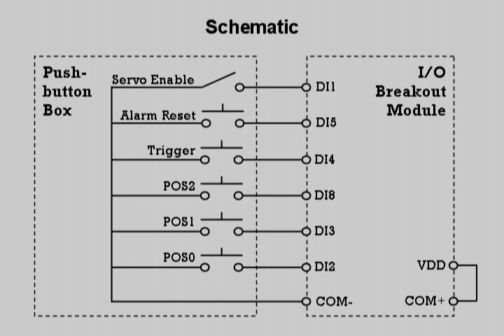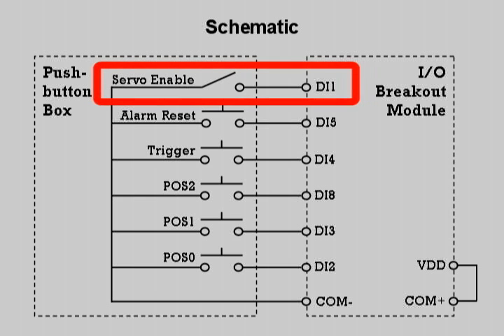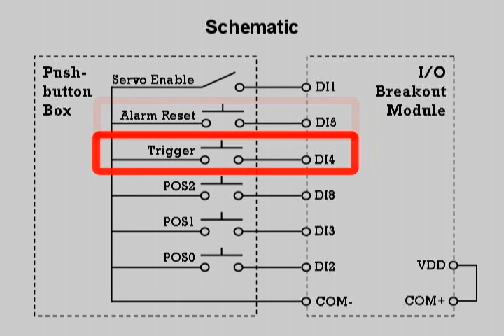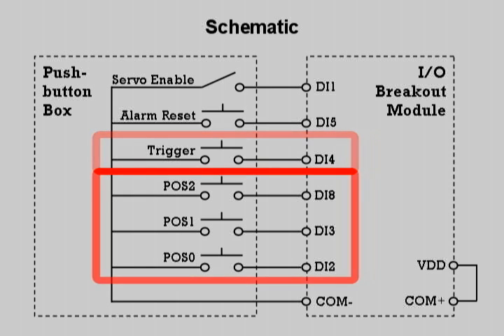Here is a schematic that shows our connections. For all the buttons and the switch, I've wired one leg of each to the COM minus connection. The switch is connected to digital input 1, this will be the servo enable. The black momentary button is wired to digital input 5, this will be the alarm reset button. The green momentary button is wired to digital input 4, this will be the trigger to actuate the moves. The three maintained buttons are wired to DI2, DI3, and DI8. These will be used to select from eight predefined positions.